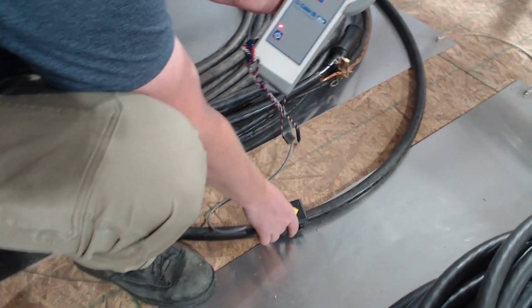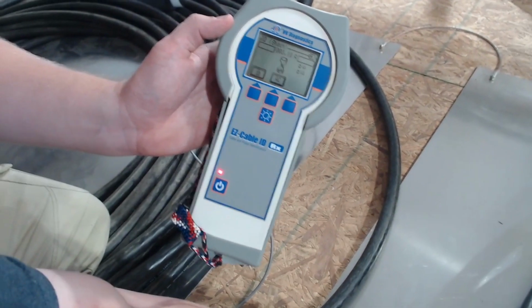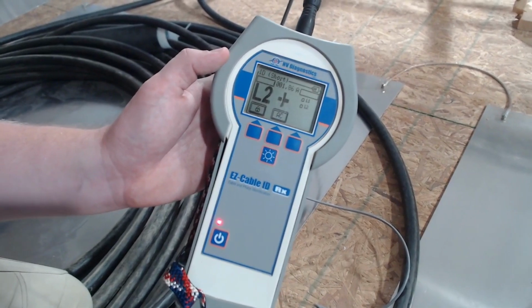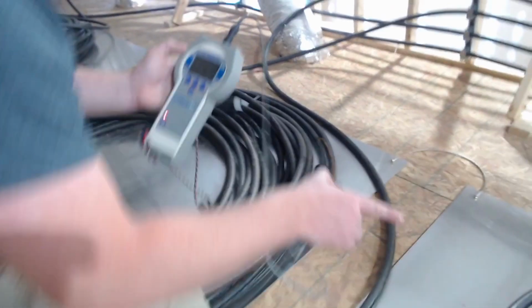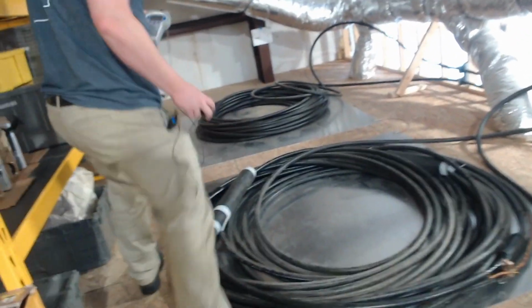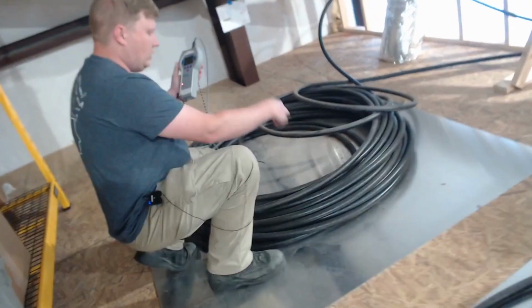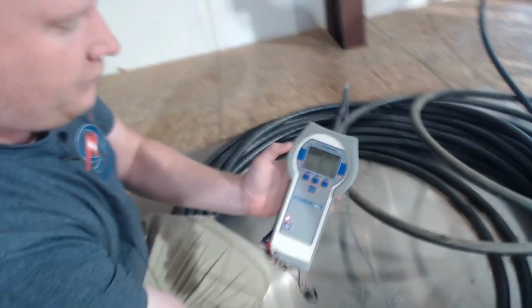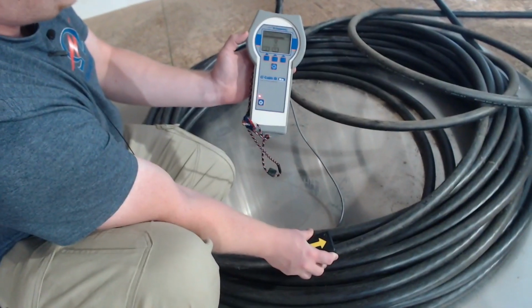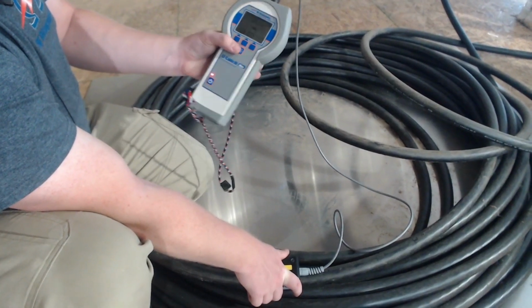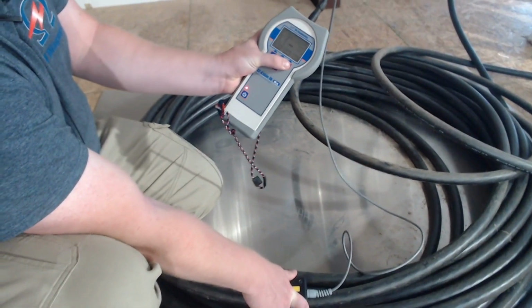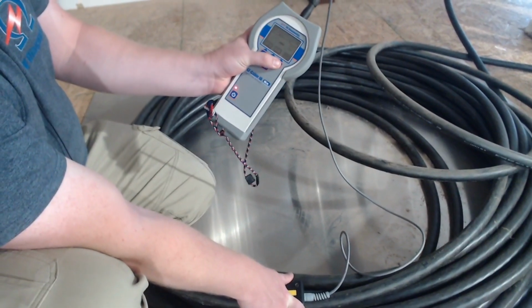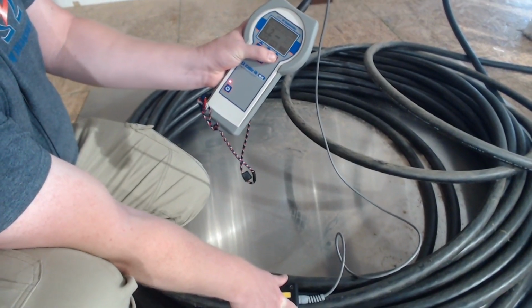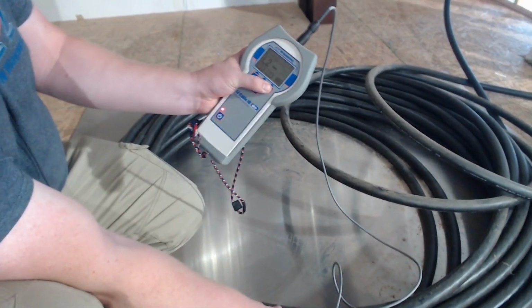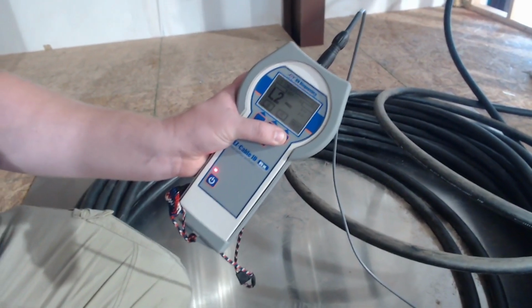Now we come over to our other cable. Now it's identifying again. So now it's telling us that we have L2 positive. So we have L1 positive for sure on our cable to our right, L2 positive on our cable over here. So now if we come to our third cable, we'll put our puck on. Now we should be seeing a negative signal, and it should be identifying negative. So if we hit our ID button, it says L1, hit ID again, L2, I might have to hold it, L1, L2. So now it's seeing both of these charges, unique signals coming down the line, and it's now showing that this is the 3rd phase.